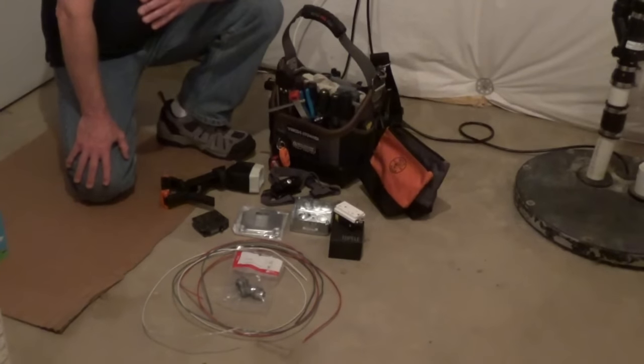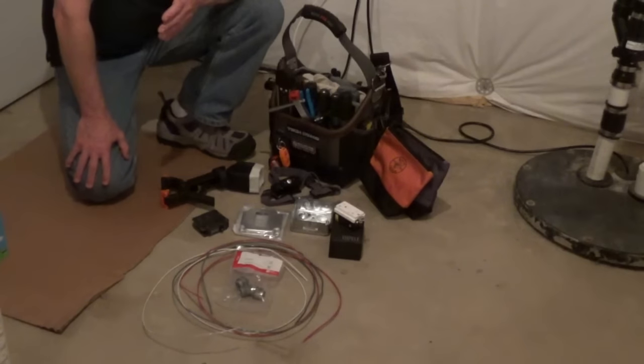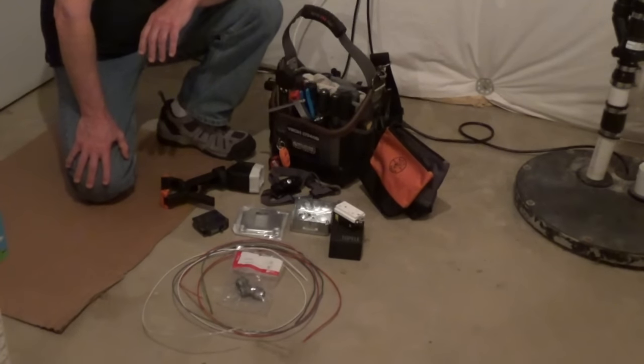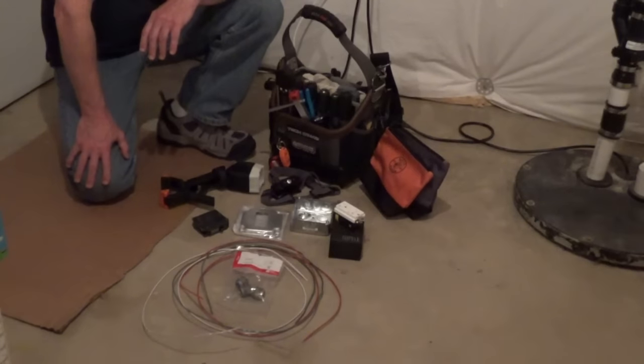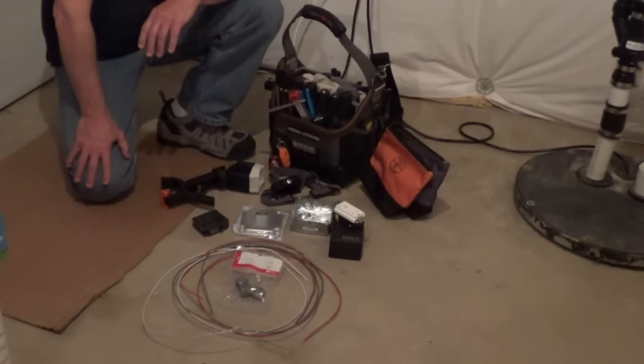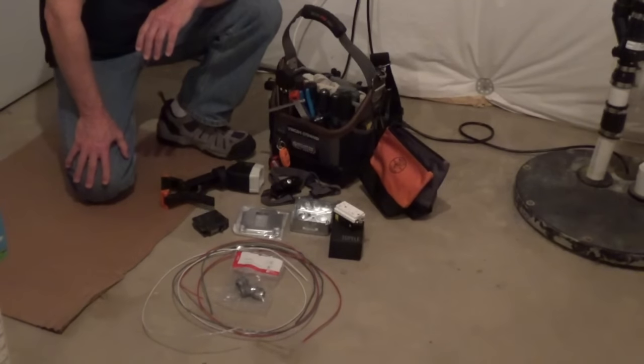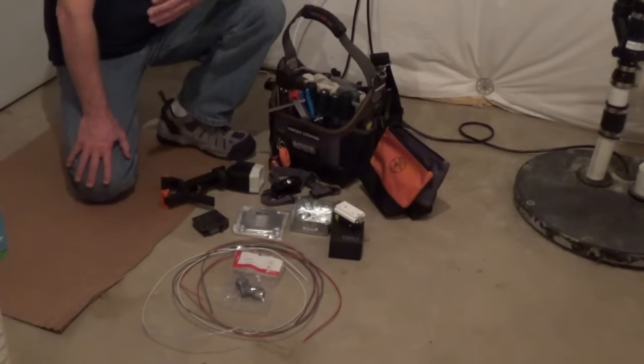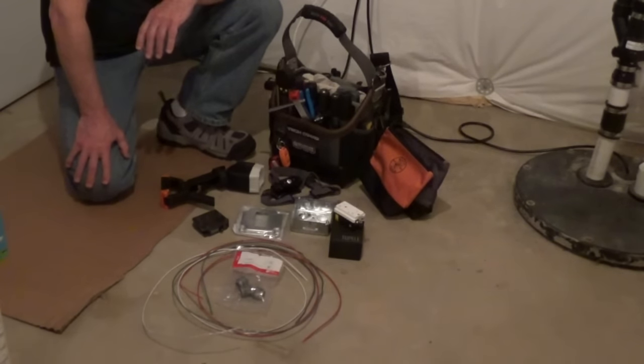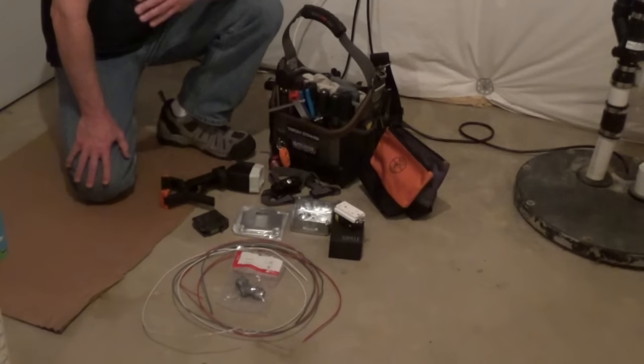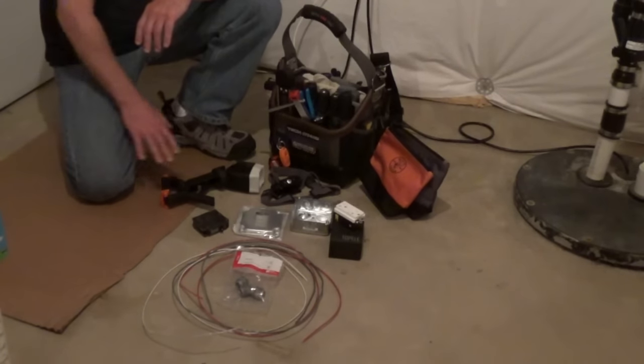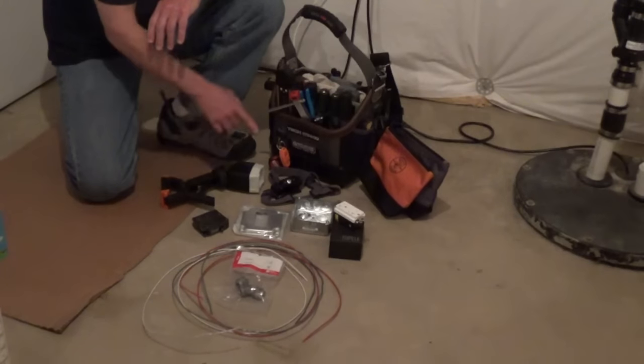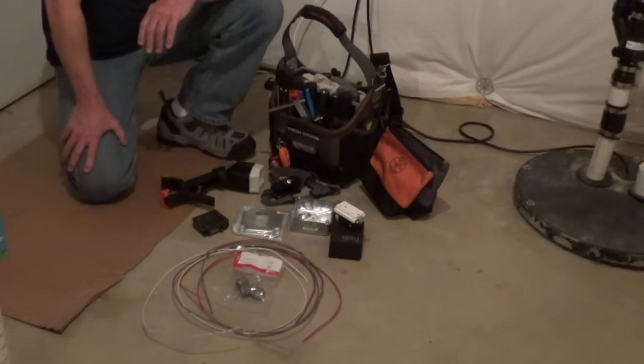For this project, I'm putting in a 20-amp GFCI because it's an unfinished basement. I have a 4-inch metal box, a GFCI cover. I have a 20-amp breaker that matches the electrical panel, and I'm using 12-gauge wire because it's a 20-amp circuit. I have box spacers to connect the box to the electrical panel, and I'm using a clamp light and also a headlamp.